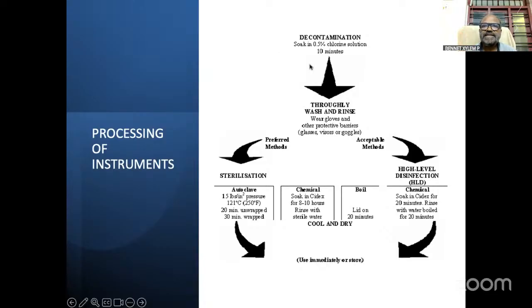So keep it in that fluid for 10 minutes. After 10 minutes, if you keep it, it will cause erosion. So better avoid after 10 minutes. Thoroughly wash and rinse, wear gloves and this. Then you take it for high-level disinfection. So what is high-level disinfection? Here again, it is very, very important. It is a Cidex solution only.